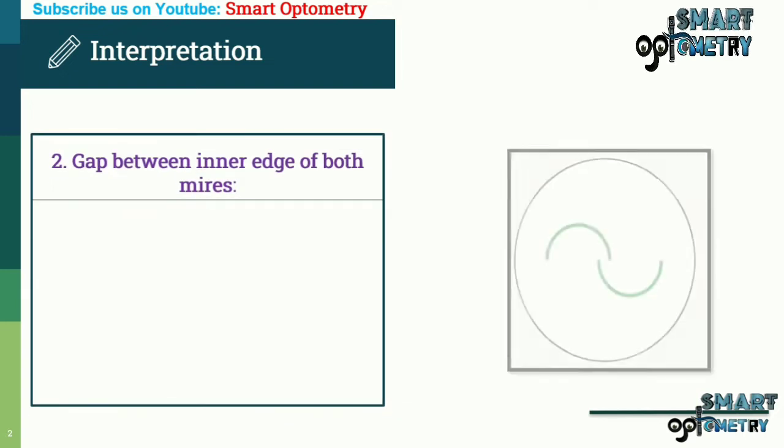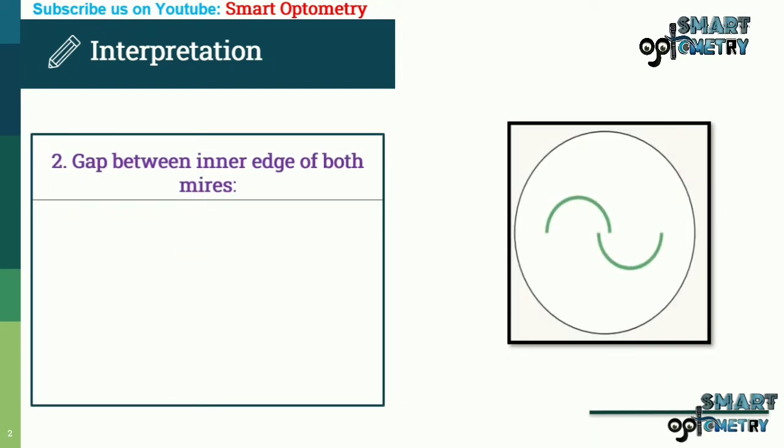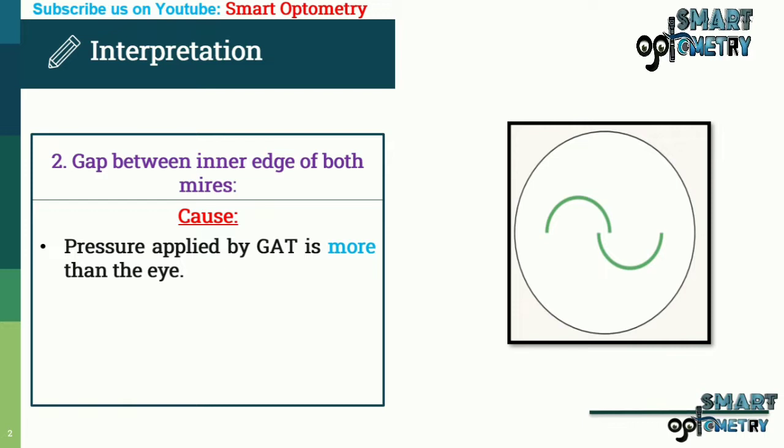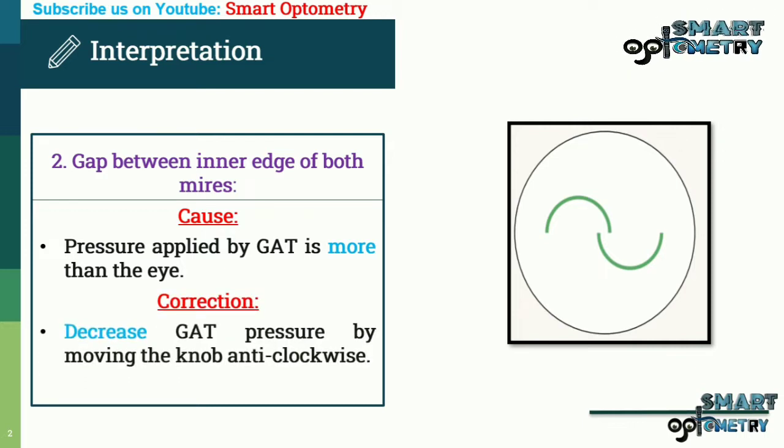Gap between inner border of both mires. This occurs if the pressure applied by GAT is more than the eye. It is corrected by decreasing GAT pressure by moving the knob anti-clockwise.